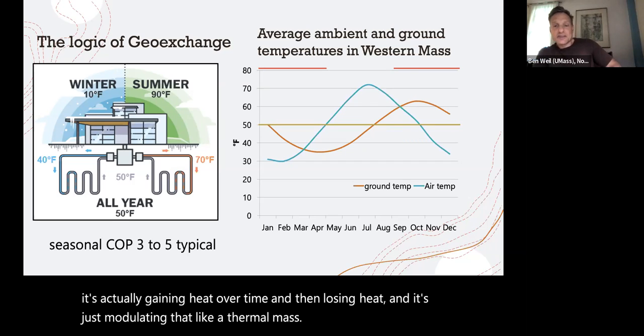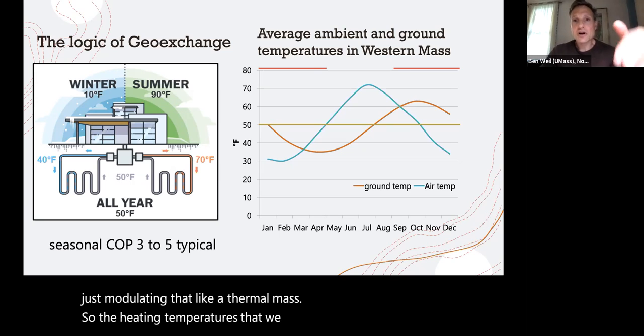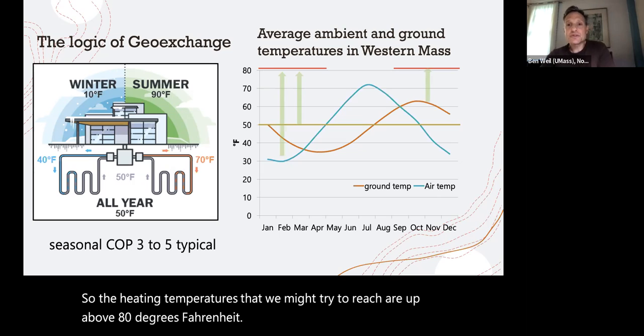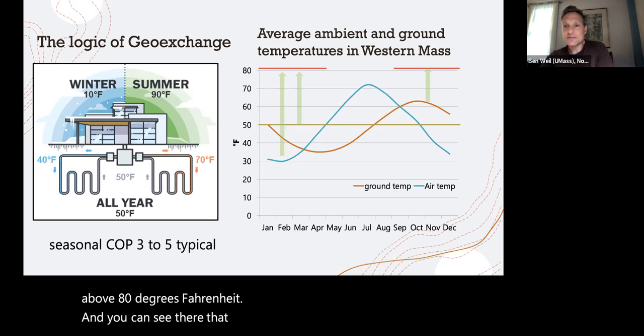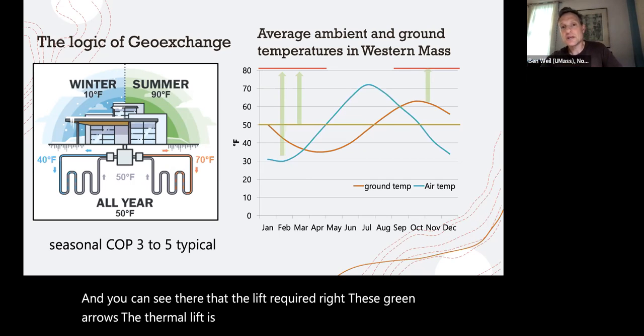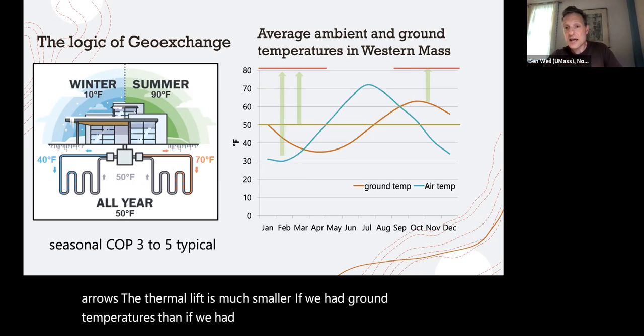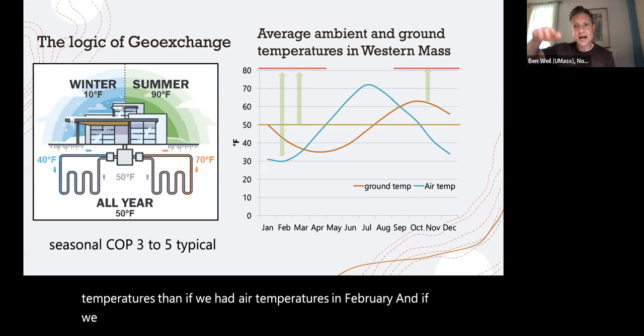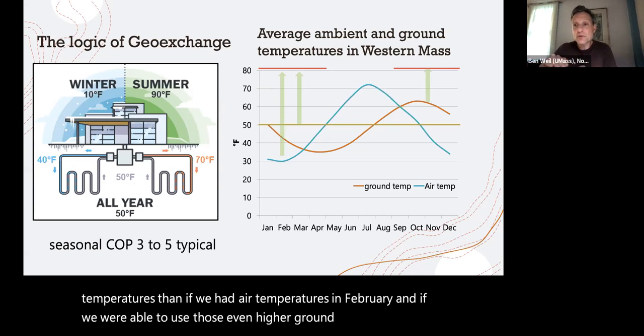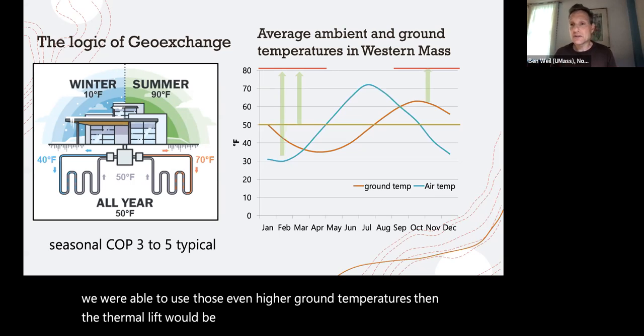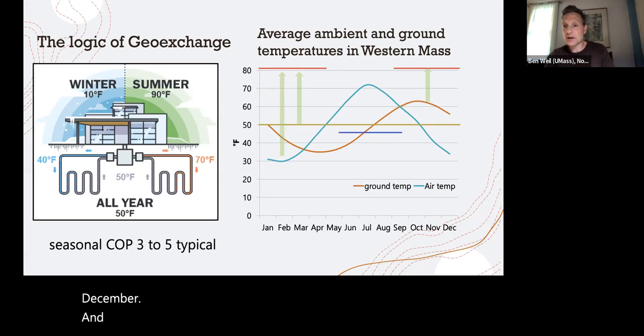So the heating temperatures that we might try to reach are up above 80 degrees Fahrenheit. And you can see there that the lift required, these green arrows, the thermal lift, is much smaller if we had ground temperatures than if we had air temperatures in February. And if we were able to use those even higher ground temperatures, then the thermal lift would be even smaller in November and December. And for cooling, it gets even better.